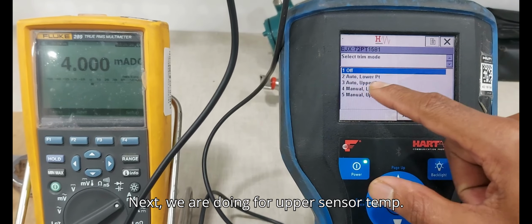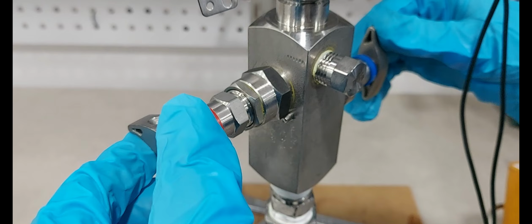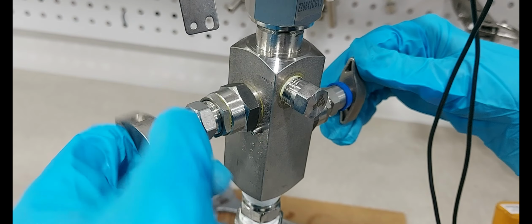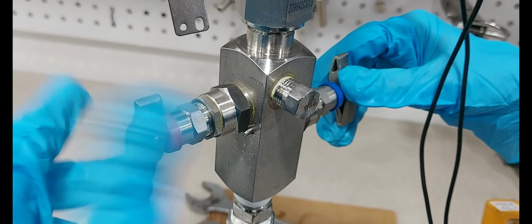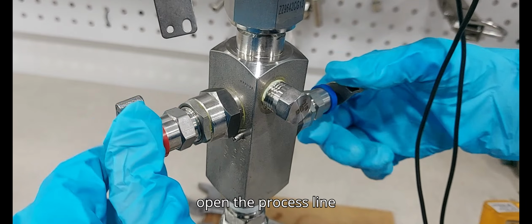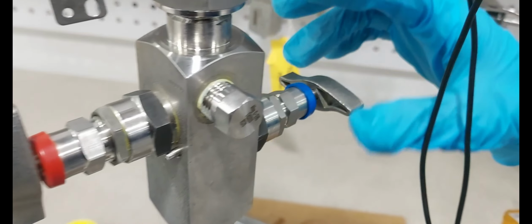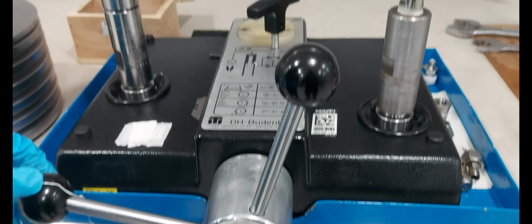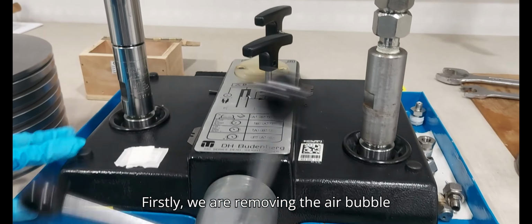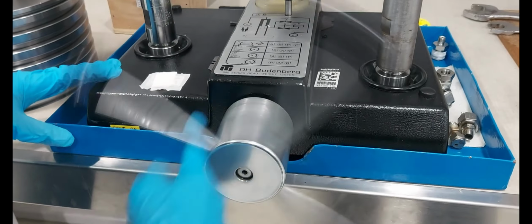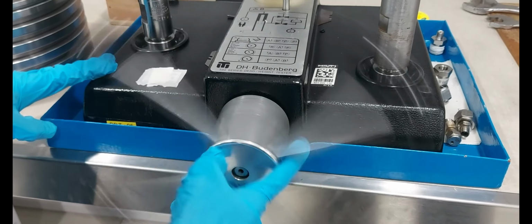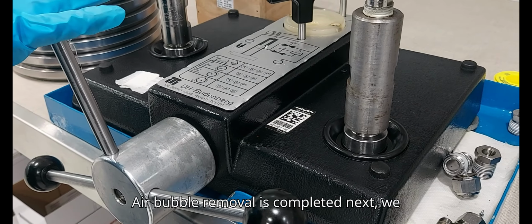Next we are doing the upper sensor trim. Next close the vent line. Open the process line, already open. First we are removing the air bubble in the dead weight tester. Air bubble removal is completed.